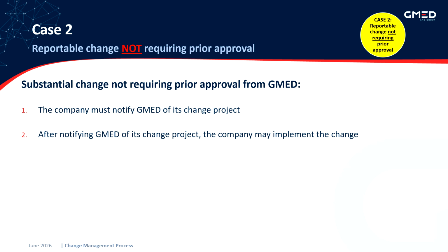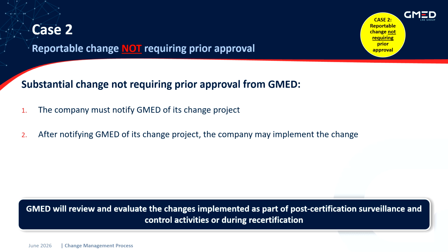For its part, GMED will review the change project notified by the company and will then evaluate the implemented change as part of post-certification surveillance and control activities or during recertification, in accordance with the applicable conformity assessment procedures.